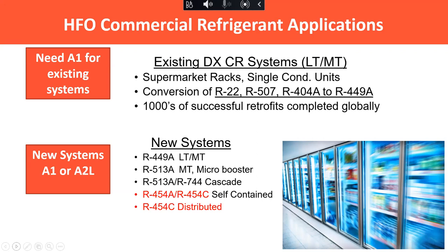But again, we see those lower GWP flammable refrigerants coming in. Will they ever be in a huge supermarket rack with 1,000 pounds or 1,000 kgs of refrigerant in there? We don't know. Personally, I don't think so. I think the supermarket industry is moving to a lot of different architectures and types of systems to help with energy. It will also reduce charge size. So all that will be factored in where and when exactly flammables show up in new commercial refrigerant equipment.